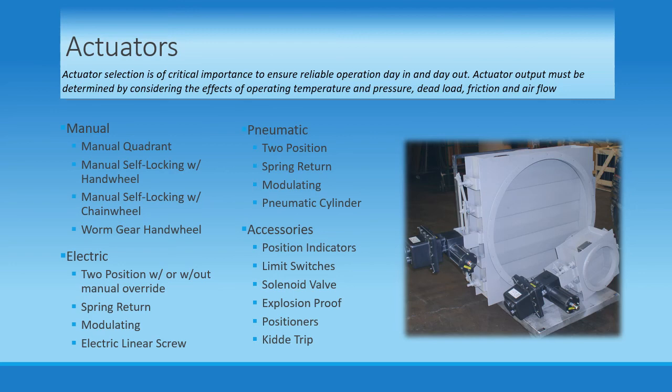Electric actuators use an electric motor to move the damper blades and rely on an electric power supply to operate. It is important to consider all aspects of the power supply — voltage, frequency, and phase — as well as the environment the damper will be in: explosive, spark-free, wet, dirty, or exposed to hazardous materials.